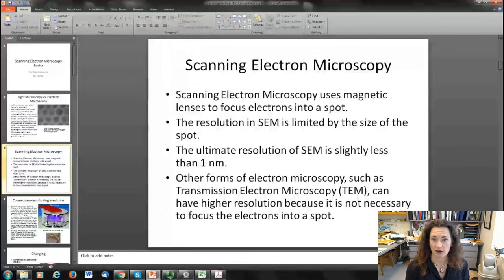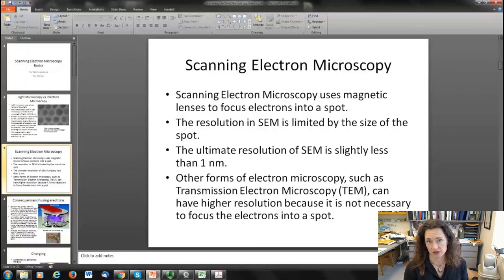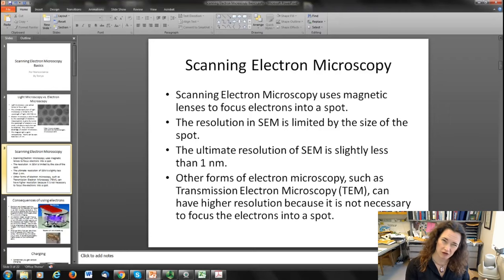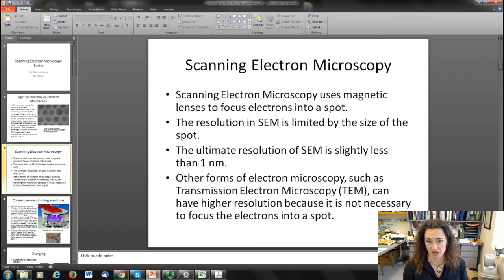Scanning electron microscopy uses electromagnetic lenses to focus electrons into a spot. The resolution in SEM is limited by the size of the spot you can focus down to, and the ultimate resolution of SEM is roughly one nanometer because it's difficult to focus the spot down to smaller than that diameter. Other forms of electron microscopy like transmission electron microscopy have higher resolution because it's not necessary to focus the electrons into a spot to take the image.